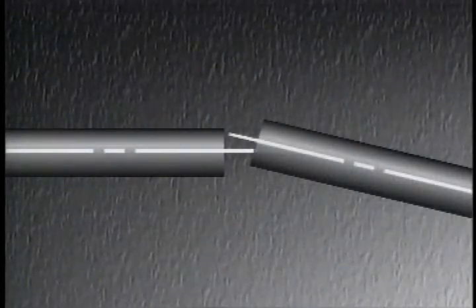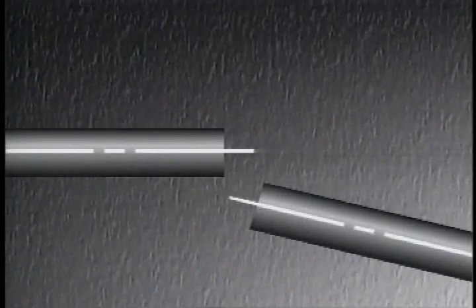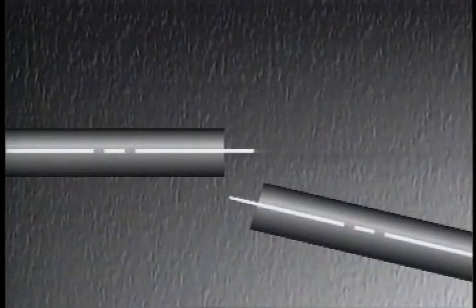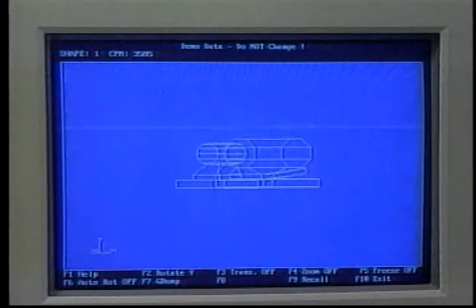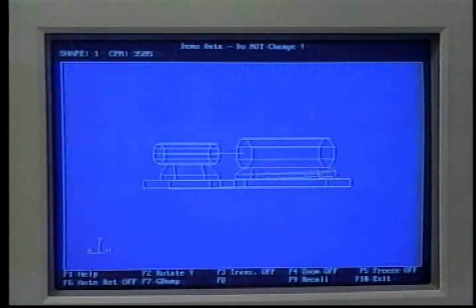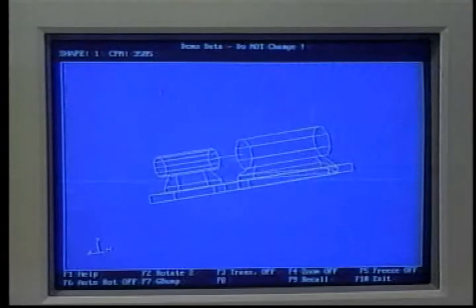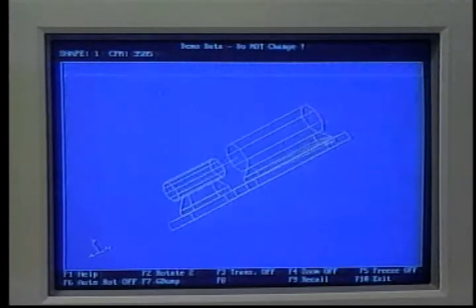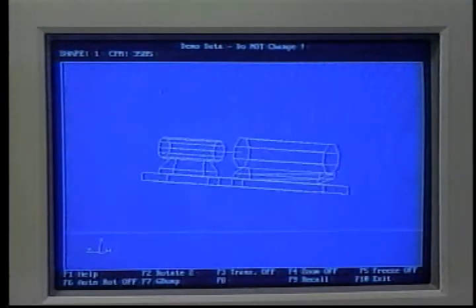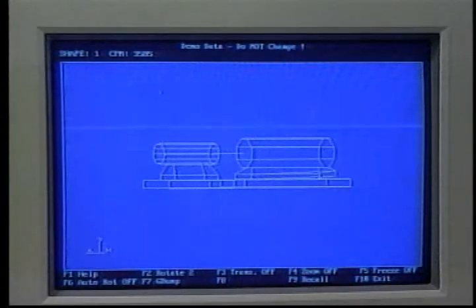Second, angular misalignment occurs when the long axis of one shaft crosses the long axis of the other. And third, combination misalignment indicates the presence of both parallel and angular misalignment, and certainly this is the usual case. The computer simulation shown here demonstrates the stresses combination misalignment can place on equipment. The left and right movement of the shafts is typical of parallel misalignment, and the flexing visible in the base of the unit suggests angular misalignment.